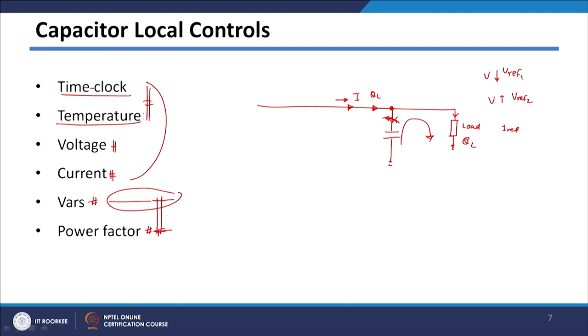And similarly here there will be power factor based control, where the power factor of the system will be measured, and based on the system power factor the capacitors will be controlled. So, these are the various capacitor local controls that are used.